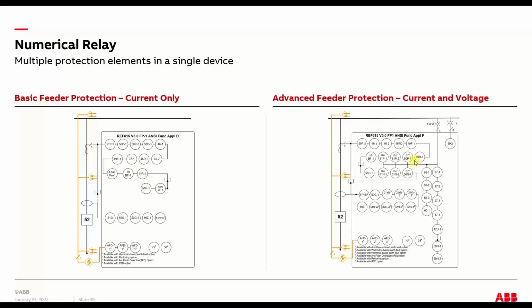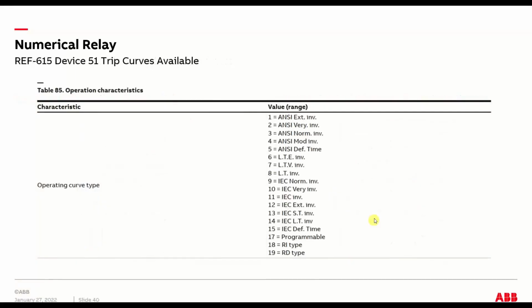And then here's a slightly more advanced relay with both current and voltage input, but still a basic feeder relay for feeder protection. And you've got a whole slew of more stuff you can do, like undervoltage and overvoltage, directional power flow, directional overcurrent, frequency, just tons and tons of things that you can do with a single box.